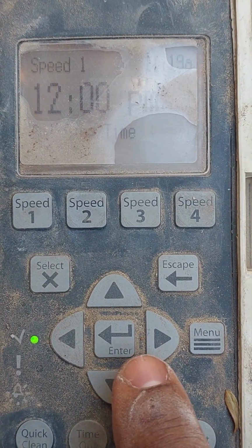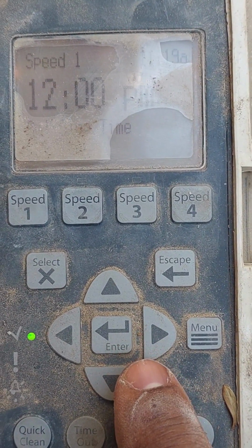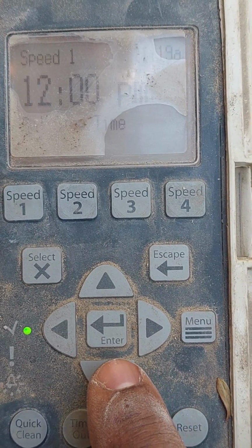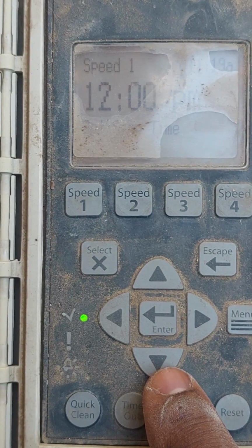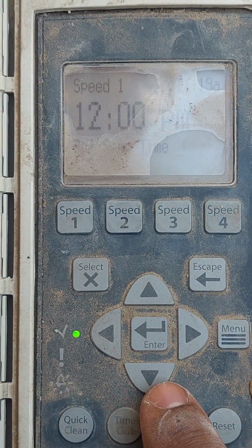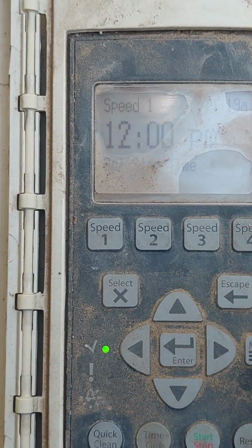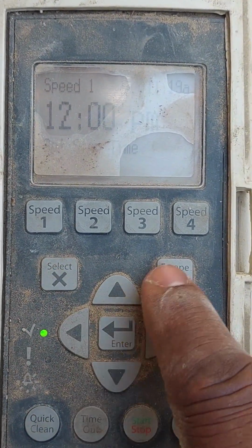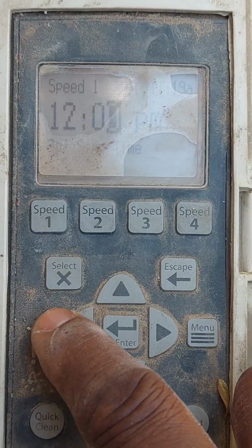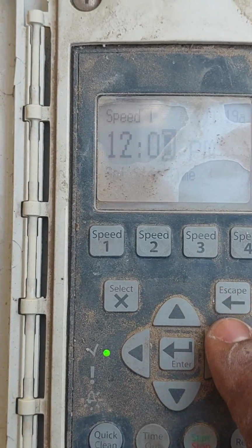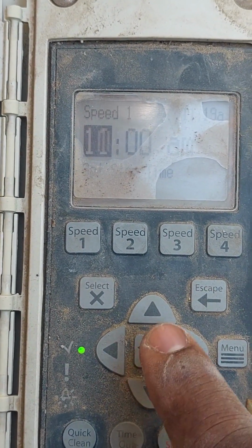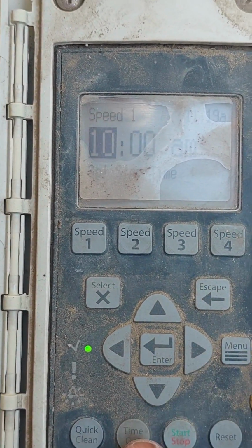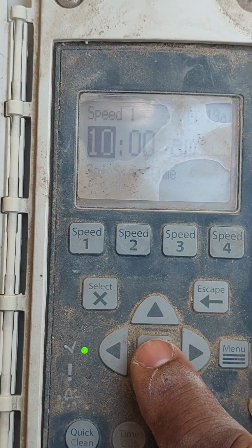Actually, we're going to kick it up another. We're going to run it 4 hours, which will give us 12,000 gallons of turnover time. So we're going to 6, 7, 8, 9, 10. So we're going to change this from 12 to 10. So we're going to select, so it's going to shut off. It's going to start at 6. It's going to shut off at 10 a.m. Then we're going to enter.